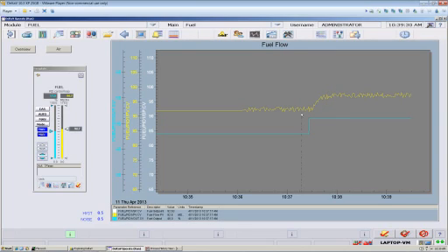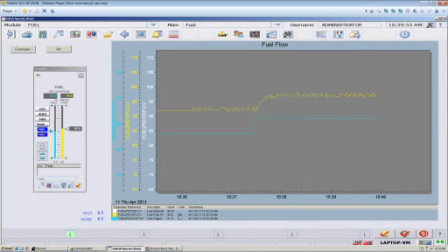Let's just click right there, partway between a peak and a valley. 92.6%, 1,000 standard cubic feet per hour, to, oh, this looks about typical of the average, 96.8, and we have 4.2. Now what about that 4.2?